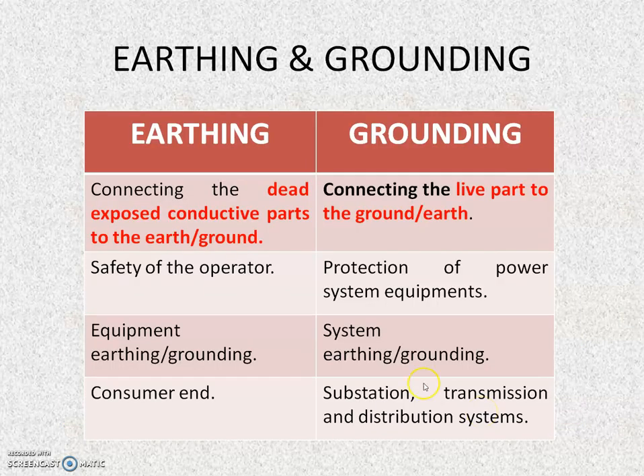Now what is the difference between earthing and grounding? Earthing is connecting the dead exposed conductive parts to the earth or ground, whereas grounding is connecting the live part to the ground or earth. Earthing is mainly done for the safety of the operator, and grounding is for the protection of power system equipments. Earthing is done at the equipment level and grounding is performed at the system level. Earthing is done at the end user or consumer end, and grounding is mainly performed at the substation, transmission and distribution system level.